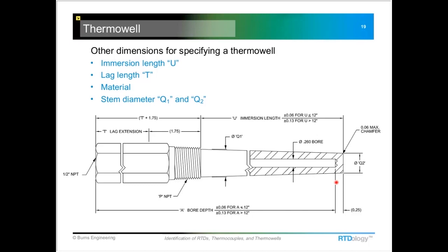These are the critical things to measure when specifying the thermowell. You should also note the diameter of the probe that came out of it. Some wells, especially for thermocouple applications, may have a bore diameter of 0.385 inches. For most RTDs, they're a quarter inch, so the bore diameter is going to be 0.26 inches.